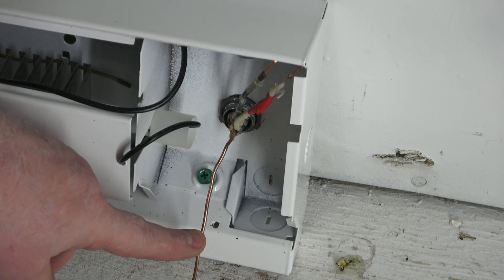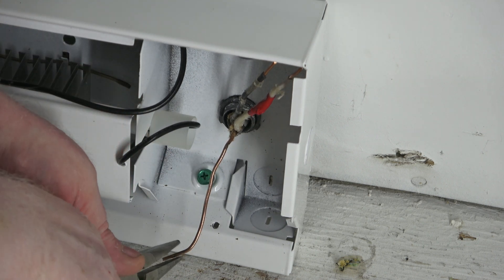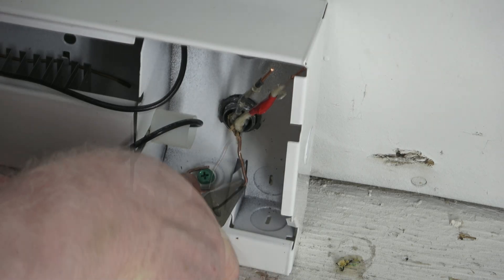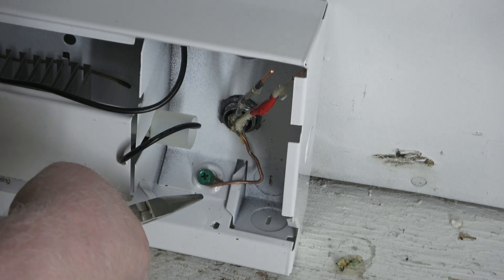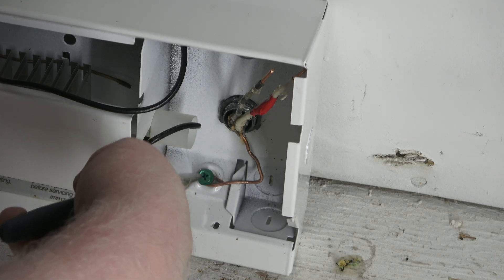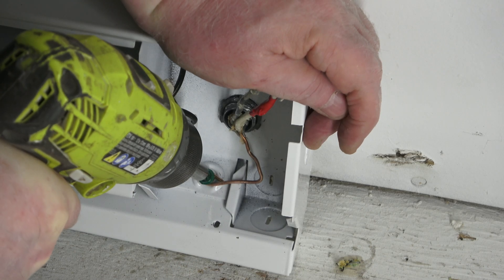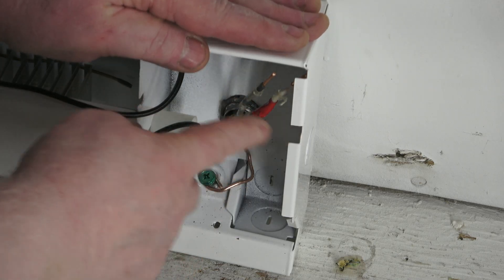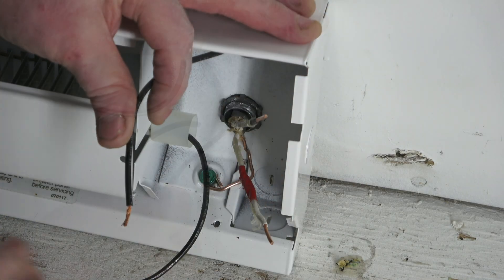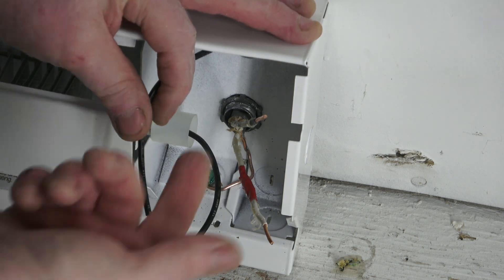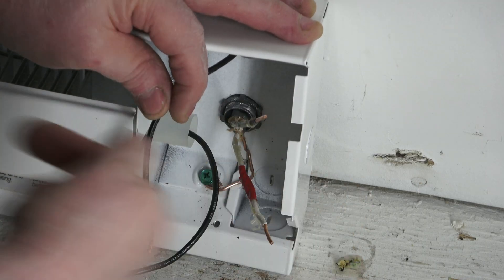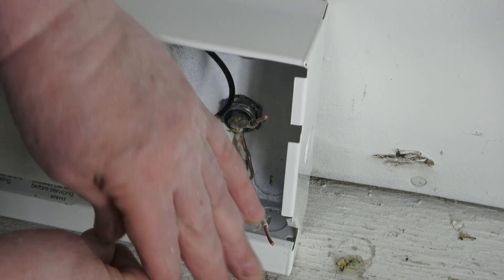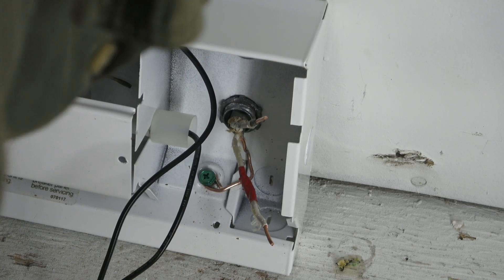And the hole I had to cut out is large enough to accept the screws in the back. So that's buried in the wall and sits flush. So we'll hook up the ground to this ground terminal. Put a little hook on there. I cinch it up. Try not to bend that wire under that wire because it might hold it up. But you want to be in a clockwise direction or it will slip out. And you've probably heard that on many videos. Now we'll power that in here. Now the case is grounded. Protection from shock. If one of these wires hit the outside, it would trip the breaker. So I just noticed when I removed the electrical cover, these were not connected. So this was already set up to be wired on the right. However, if you never opened that and you wired it from the left, the unit would not work. You'd have to come in here and make this connection. Then it would work.